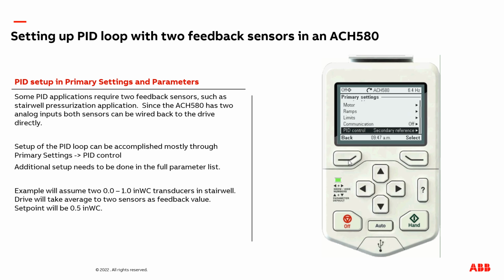Now, after this, we need to back out of primary settings and go back to the main menu here. We now are needing to navigate to the main parameter list to make the final adjustments. Go to complete list. Now, the first adjustments are going to be made in group 12, standard AI. We need to set up the second analog input source. We adjusted AI2 already, but now we need to adjust AI1 as that is connected to our other transducer.